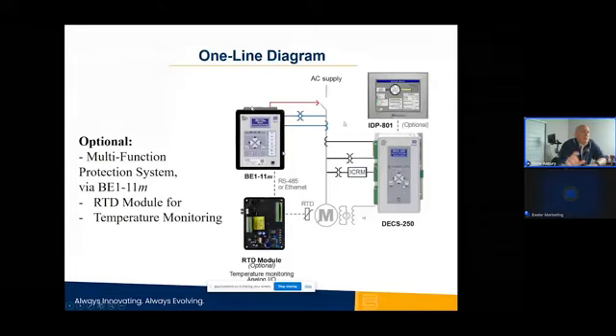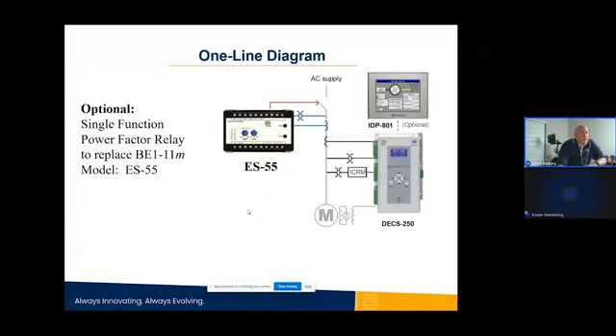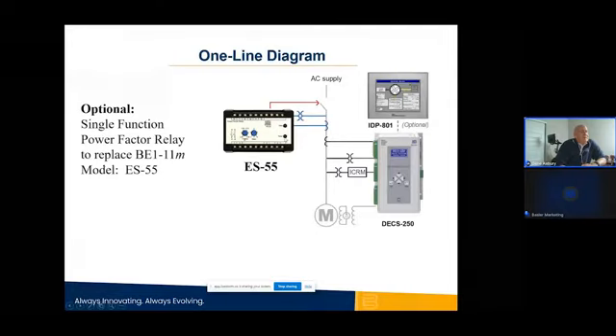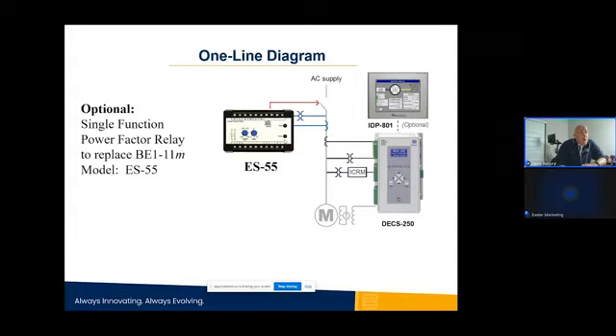If we replace this, we would replace it with a single element protection function called the ES55 relay, which is your motor pullout protection. And that's what that looks like. So it's a little DIN rail mounted device. Some of you, if you're familiar with the Basler products over the years, we used to have what we call a PRP 320, which was a motor pullout protection relay and was very popular. But we had to obsolete the part, so we had to come up with a replacement. So this product for us is doing very well.